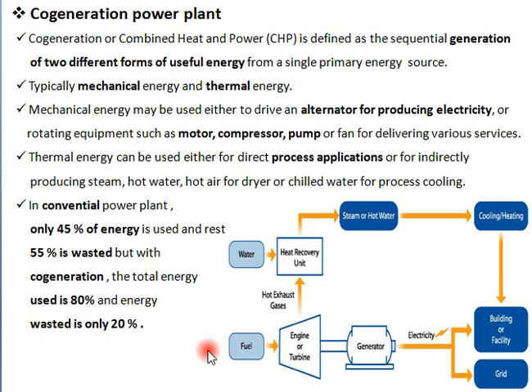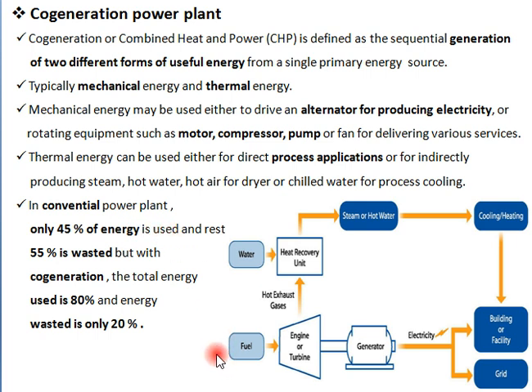This is the main principle of the co-generation power plant. Now, considering efficiency: in a conventional power plant, fuel is applied to a boiler, steam strikes the turbine, electricity is produced, and the steam is condensed. In a conventional power plant, only 45 percent of energy is utilized. The remaining 55 percent is wasted through flue gases exhausted via the chimney to the atmosphere.